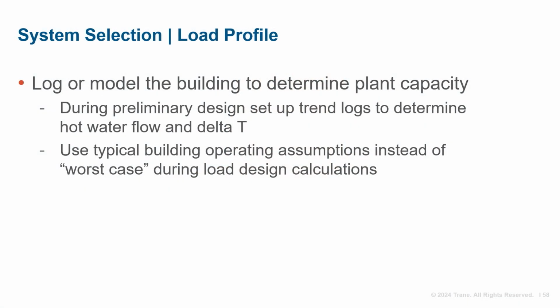Because electrified heating equipment commands a higher price tag, it may be worth the time and money to conduct a more detailed analysis. This might mean gathering trend data during winter conditions, if possible within the project timeline. If the data exists already, even better. If that's not possible, a detailed energy model is a good substitute, accounting for actual ambient conditions and building operating schedules. The designer must carefully balance risk management without oversizing the central plant.